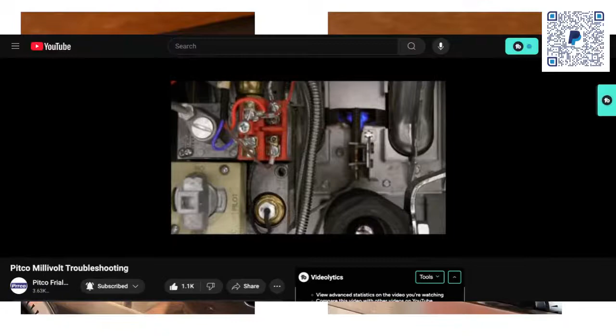You will need to make these pilot adjustments in order to get the proper millivolt output from your thermopile. Proper thermopile output with only the pilot on should be approximately 600 millivolts plus or minus 50. Once the burners ignite, your millivolt output should drop approximately in half.